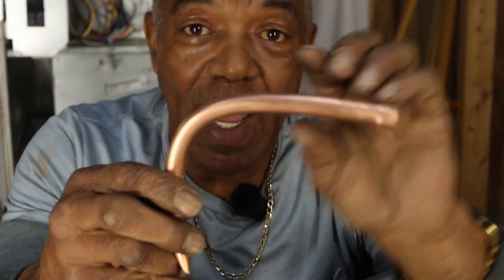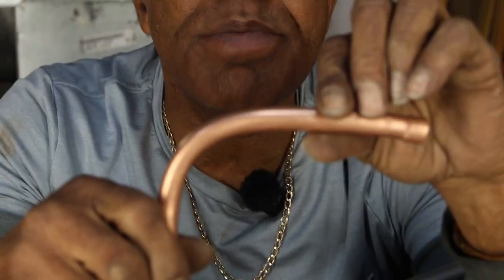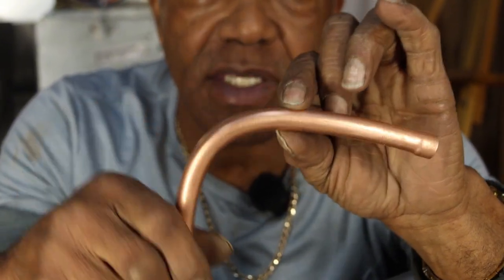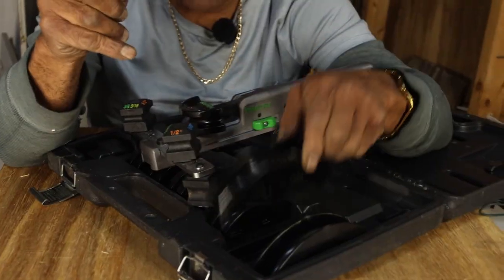because an elbow has to be brazed on this side and an elbow has to be brazed on this side. That's a potential leak. That's 2 potential leaks. That's solid copper. There's no possibility of a leak. So I can use this tubing bender and I can fit my copper in almost any application. I can bend it, whatever size it is, based on the different heads. I can use this to manipulate my copper to make my installation a great deal easier and cost a great deal less time.